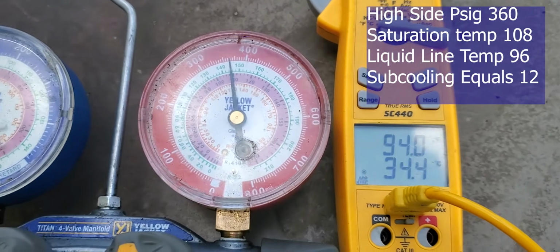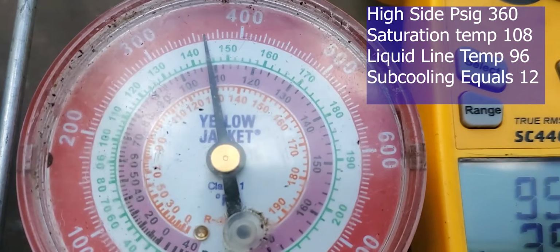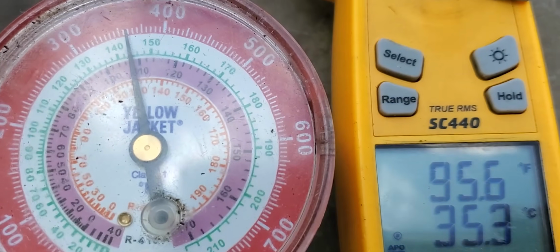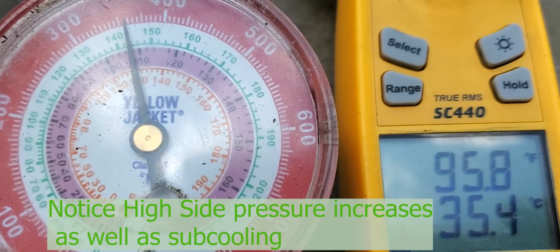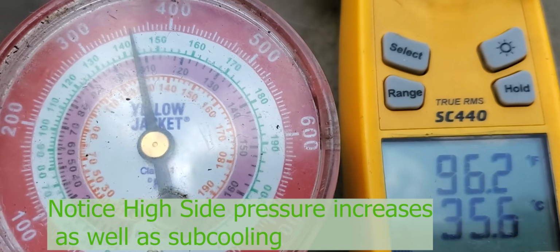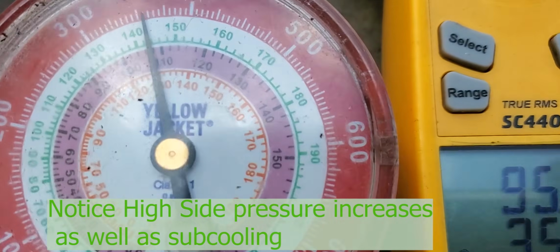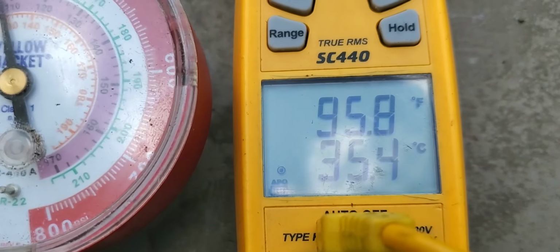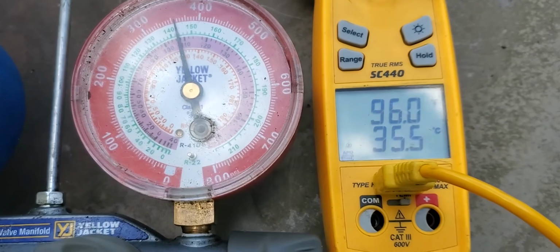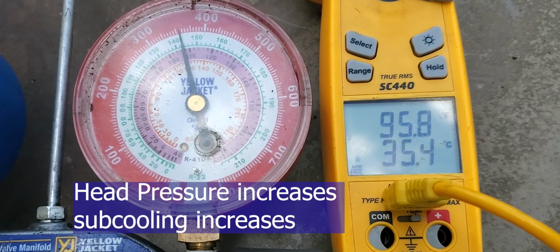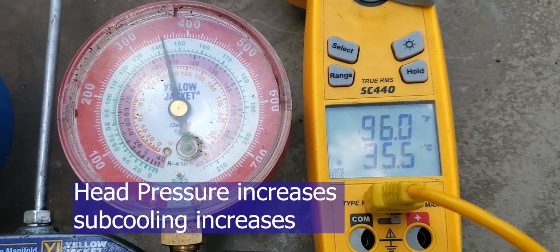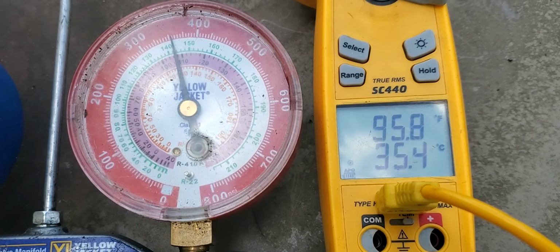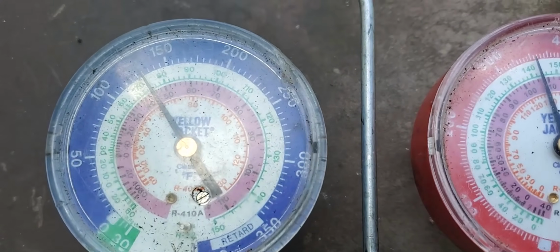So the superheat is how much liquid is in the evaporator. The subcooling is how much liquid is in the condenser. You can tell that both pressures, low and high side, have increased. And now our subcooling is around 12, whereas we needed a subcooling of around 10. So that means we're reaching the point where we know that our unit is almost charged.